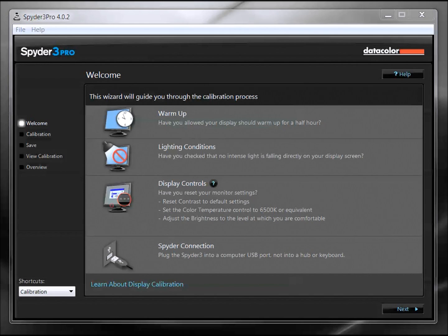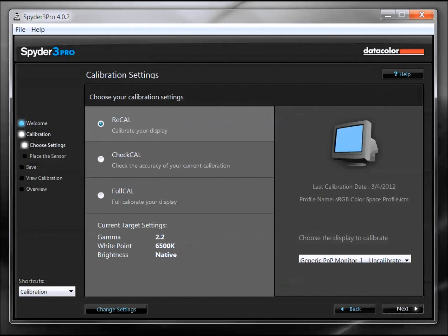The next one is the display controls. It asks if you reset your monitor settings, contrast, color temperature, adjust the brightness, and then the Spyder connection for the unit needs to be plugged right into the computer USB port. Do not run it through a hub or the keyboard. Plug it directly into your PC tower. So when we're done with that, we click Next.